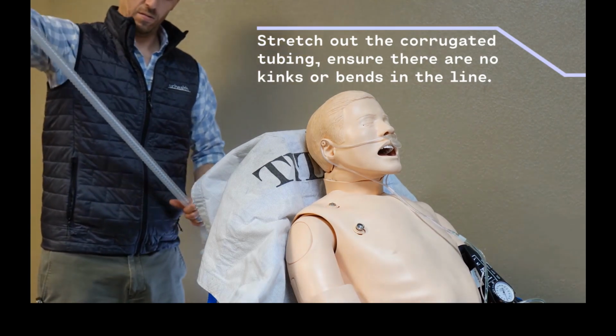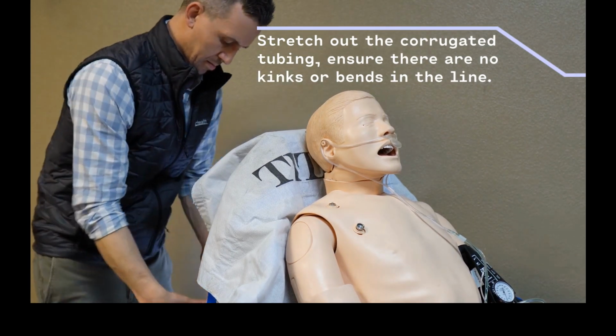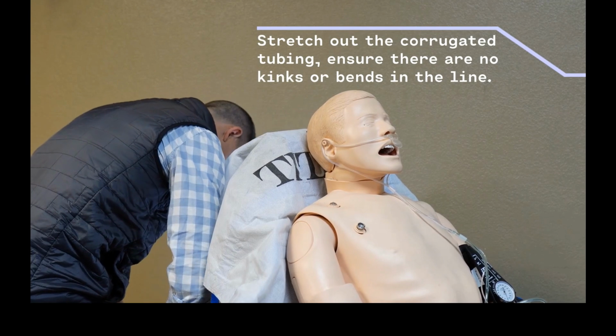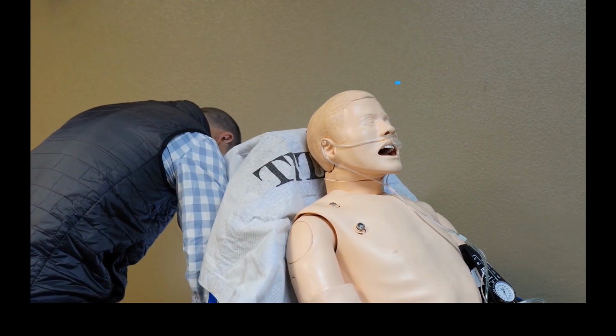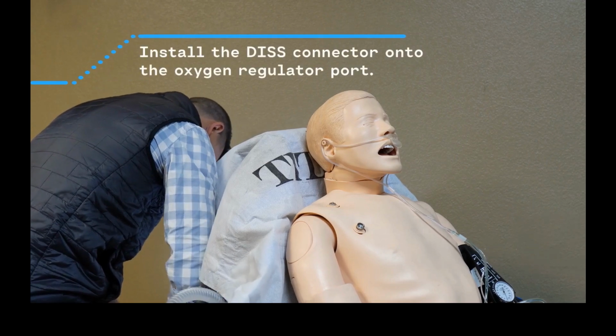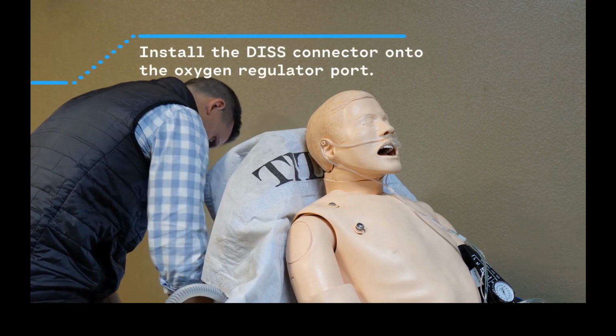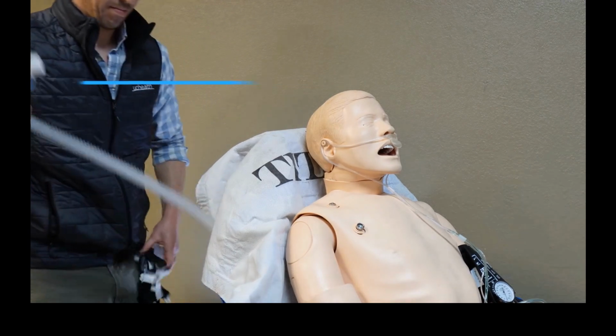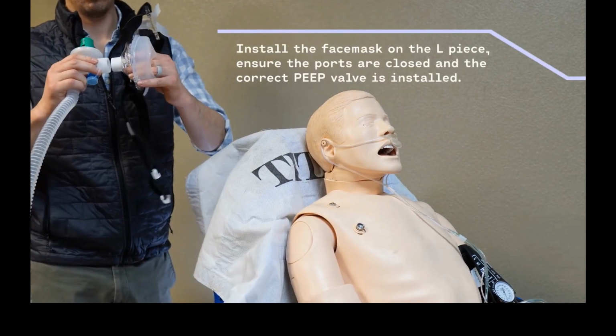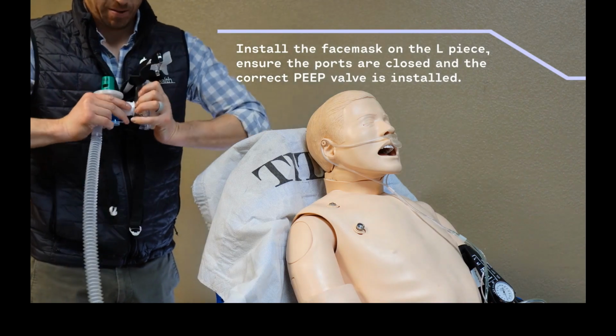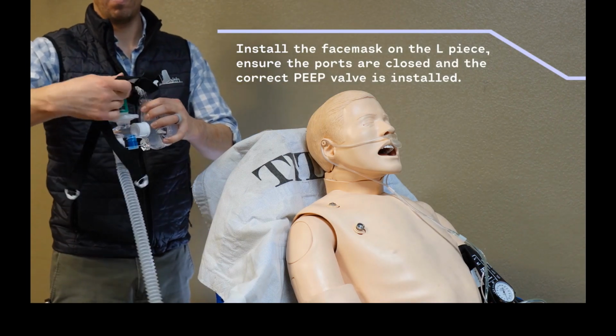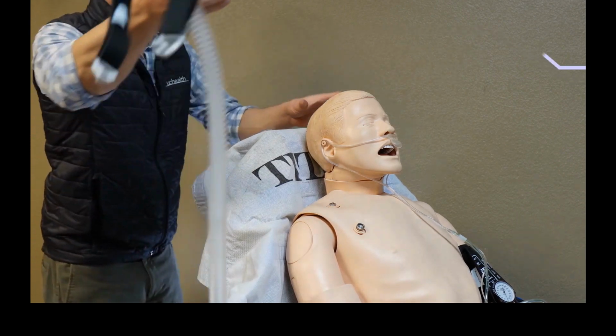Stretch out the corrugated tubing, ensuring that there are no kinks or bends in the line. Then, you're going to install the DISS connector onto the oxygen regulator port. Be careful not to cross the threads. Install the face mask onto the L connector and make sure that it's seated. Also, double check that all the ports are closed and you have the correct PEEP valve.